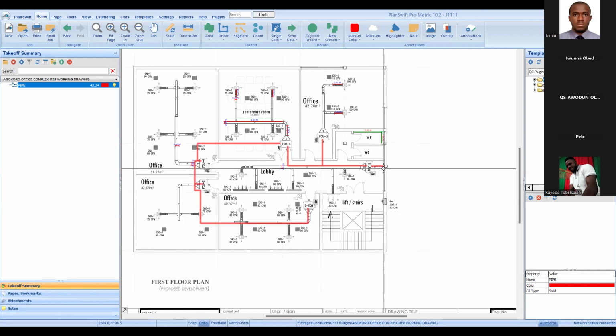And we have 6 meters, based on this one being on the ground floor and the first floor. The height of a building is 3 meters. First floor, 3 meters. Ground floor, 3 meters. Now, that's 6 plus 42, we have 48. And let's not forget that at every point there will be a termination. This cable is a flexible cable, and it is 4 core by 4 mm cable. It depends on what is being recommended. Some electricians will tell you 4 core by 6 mm cable.